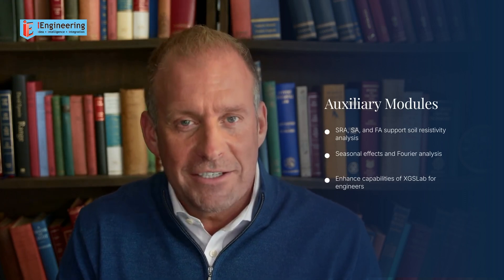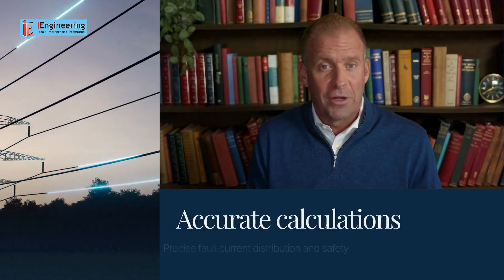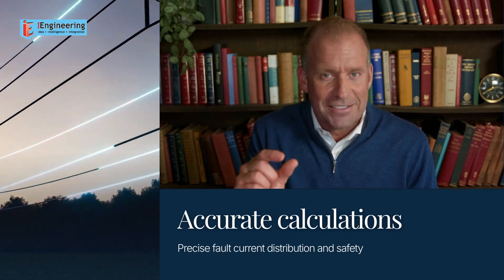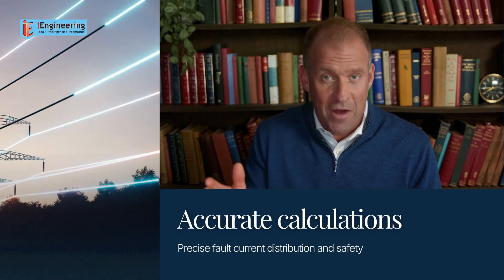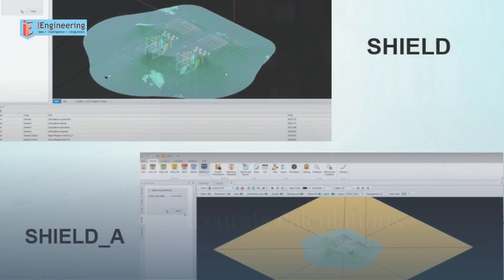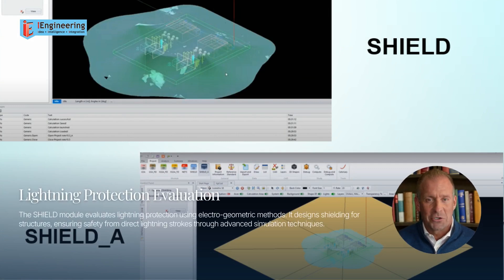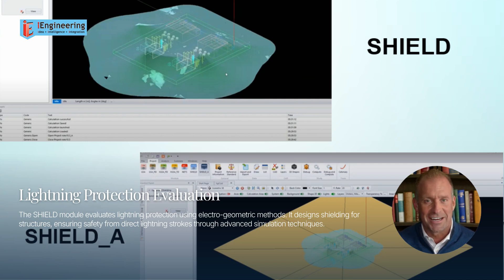Auxiliary modules like SRA, SA and FA support soil resistivity analysis, seasonal effects and Fourier analysis. These tools enhance the capabilities of XGSLAB, providing comprehensive solutions for engineers. The NETS module accurately calculates fault current distribution and electromagnetic interference, considering alternative return paths and ensuring precise results for earthing system sizing and safety. The SHIELD module evaluates lightning protection using electro-geometric methods, designing shielding for structures and ensuring safety from direct lightning strokes through advanced simulation techniques.